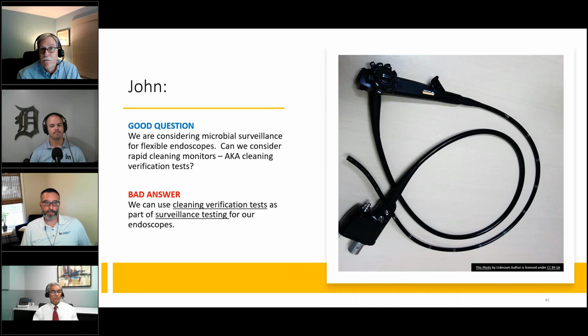It's part of focused inspection after manual cleaning. Cleaning verification, as the name implies, is testing for cleaning efficacy. So it's indicating the presence of residual organic soil, such that if positive, this allows for the re-cleaning and retesting of the device prior to disinfection.